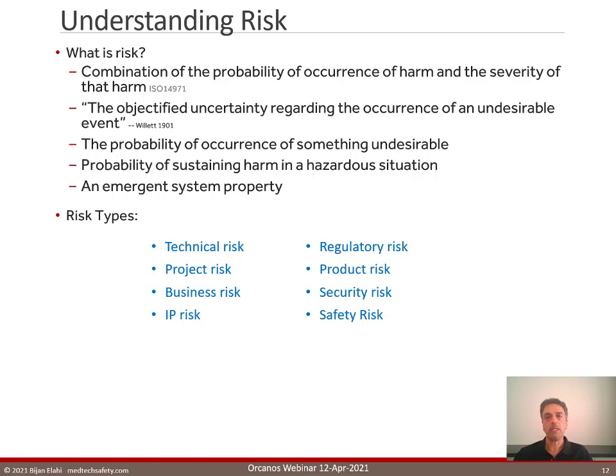When a CEO is talking about risk, he or she is talking about business risk. What's the probability of losing money on this project? Here I'm talking only about one type of risk, and that is safety risk. And even that comes in 2 flavors. Risk to the health of the patient or the user from the use of a medical device, and EHS risk, or environmental health and safety risk. This is a risk to your health and safety, but it's not from the use of a medical device. It's, for example, from slipping on a wet floor in the office or breathing air that is not very clean, and so on.